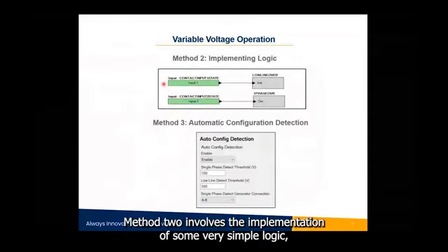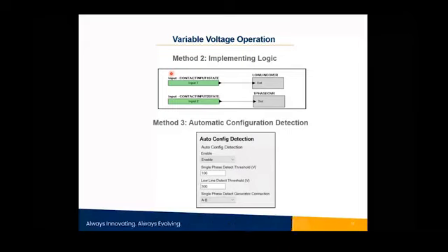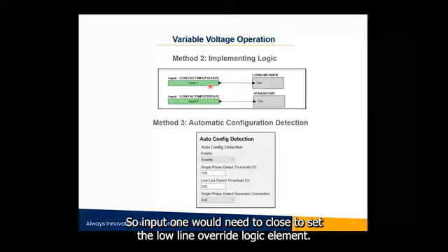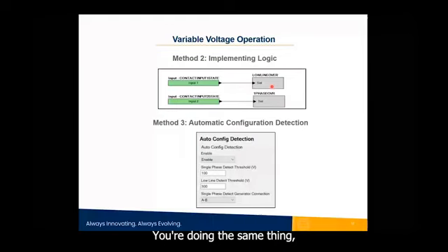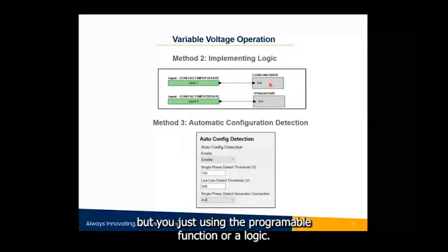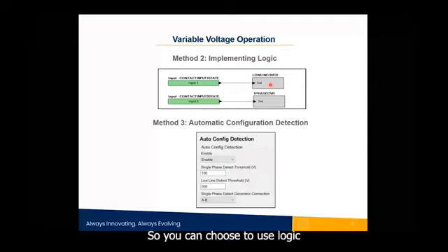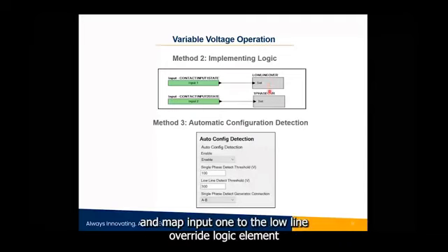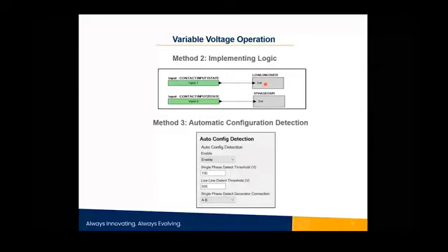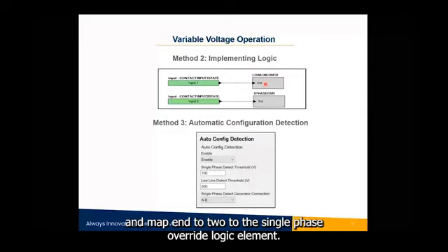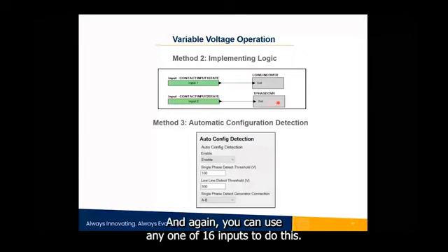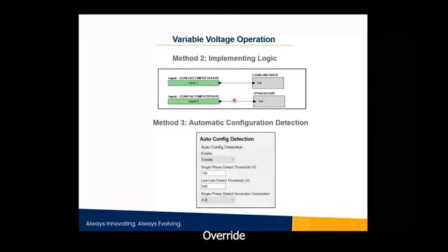Method two involves the implementation of some very simple logic. So it also entails using contact inputs. So input one would need to close to set the low line override logic element. You're doing the same thing, but you're just using the programmable function or a logic test. So you can choose to use logic and map input one to the low line override logic element and map input two to the single phase override logic element. So I've done the same thing, just using two different methods. And again, you can use any one of 16 inputs to do this. I've just chosen input one for low line override and input two for single phase override.